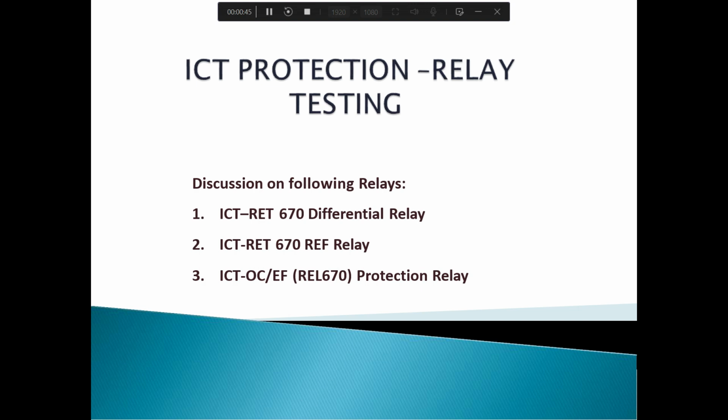differential relay testing procedure. These slides are prepared using the RET670 differential relay, but the procedure explained herein is applicable for all, that is Siemens make relays, Alstom make relays, GE make relays, or any other differential relays. The procedure will remain exactly the same with only slight differences related to the settings of a particular make of relays.